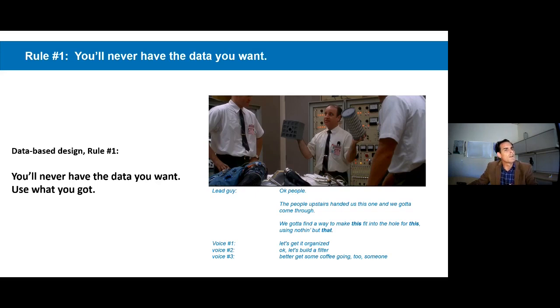So rule number 1 in existing building data analytics is that you're never going to have perfect data. You're never going to have all the data that you want. The data that you have will always be flawed. You're always going to wish that you had a sensor or a meter that was 5 feet away from where it actually is. That will always be the case. But we have to use what we have. We have to use the data that we've got.